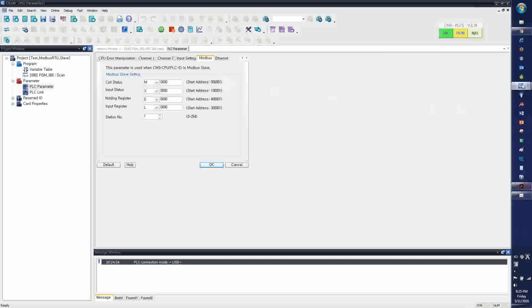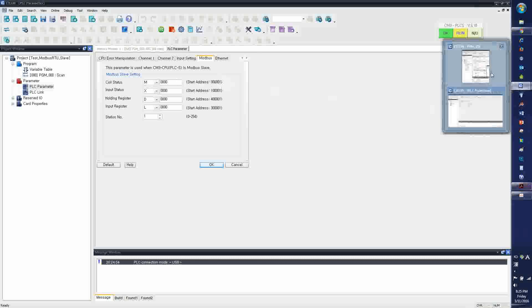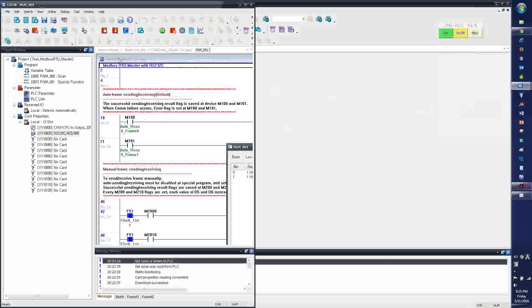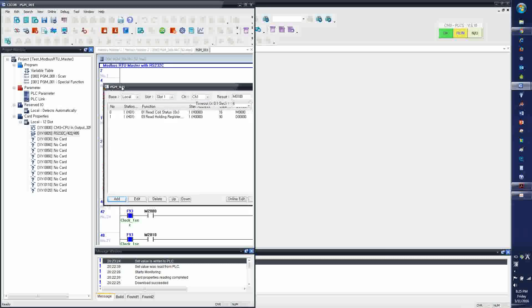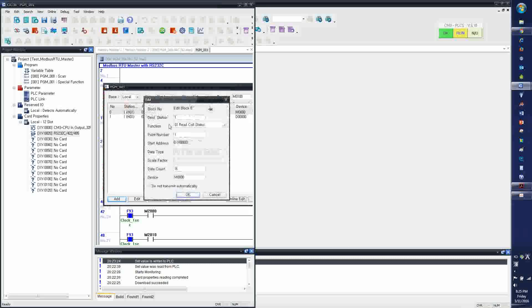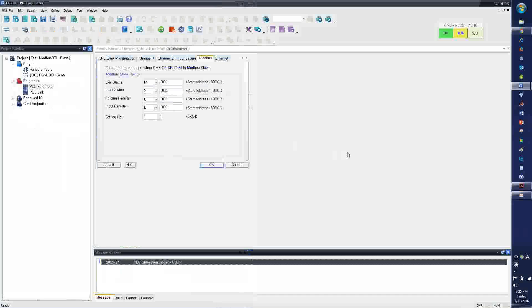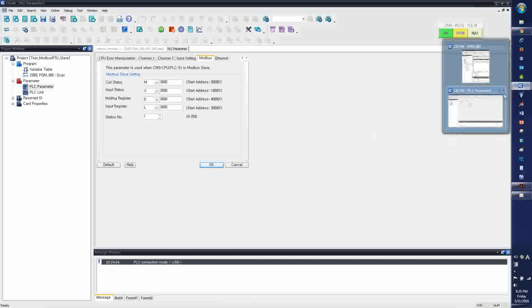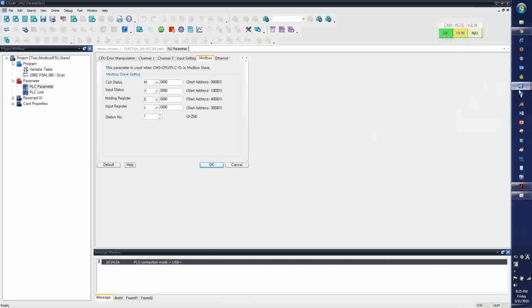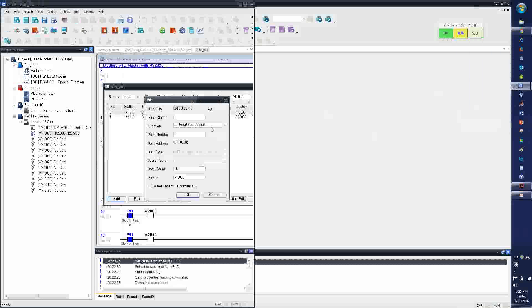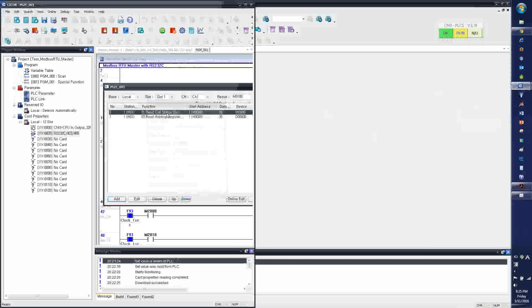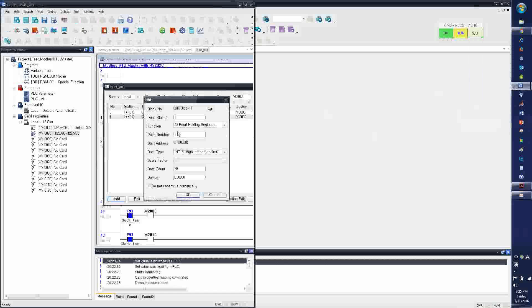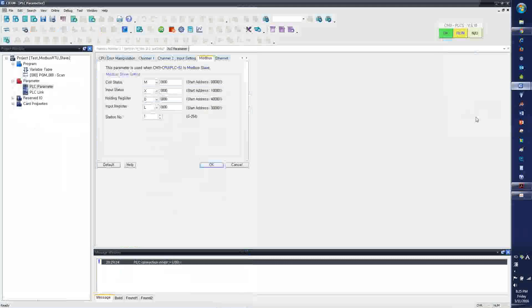Notice that the coil status, I'm linking up the M device, the CIMON PLC address, to Modicon's coil status. So the start address is 1, which is, if I go to the Modbus RTU master program, the point number here, this number was this. And also, this number here, the point number, is my holding register D, and starting begins with 1.